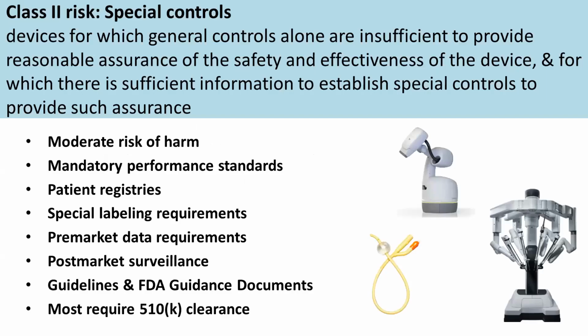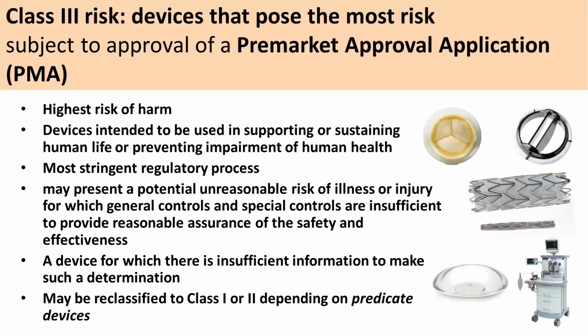Class 2 risk falls under both the general and also special controls. And special controls are usually device specific. So these are devices that could cause moderate risk of harm, and therefore the FDA wants to see mandatory performance standards. They might want to see registries, special types of labeling, some pre-market data requirements, post-market surveillance, and there might be special guidelines and FDA guidance documents for these. And we'll talk about the 510K in a moment. Class 3, these are the most potentially dangerous devices with highest risk of harm, and they are subject to a pre-market approval application, which we will also discuss.